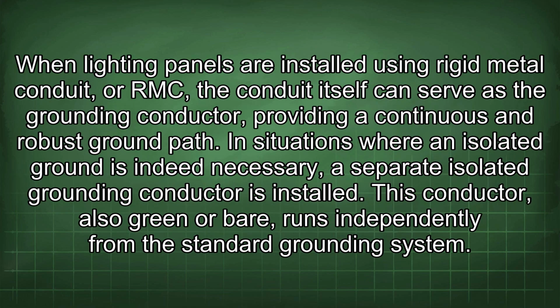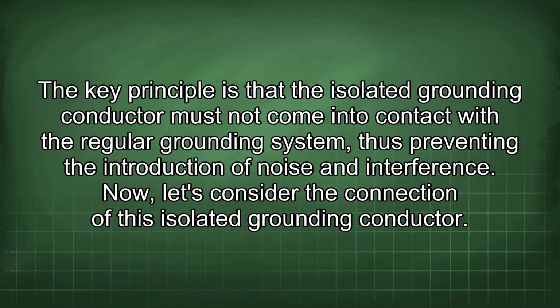When lighting panels are installed using rigid metal conduit, or RMC, the conduit itself can serve as the grounding conductor, providing a continuous and robust ground path. In situations where an isolated ground is indeed necessary, a separate isolated grounding conductor is installed. This conductor, also green or bare, runs independently from the standard grounding system. The key principle is that the isolated grounding conductor must not come into contact with the regular grounding system, thus preventing the introduction of noise and interference.